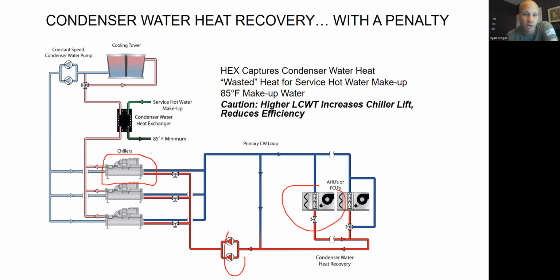But instead of sending my water out to the cooling tower to just waste the heat away, the energy code says, and this is when you're above a certain size, right? It's not every system, but when you're above a certain size capacity of your system, you have to put a heat exchanger on that condenser loop and try to save that energy. So instead of rejecting all the BTUs out into the sky, you reject as many BTUs as you can into this heat exchanger. And this heat exchanger can be used to heat your makeup air or to heat your service water, your domestic water, right?